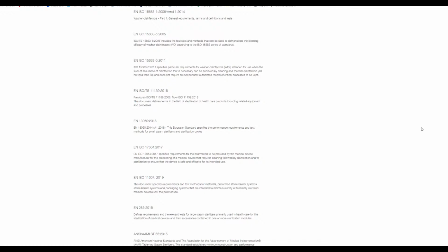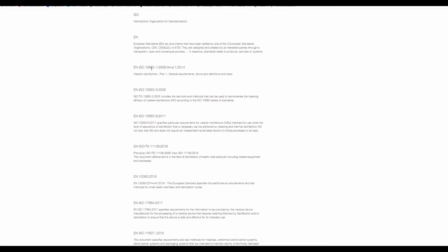What do you have to clean? Legal advice. This is, for example, the applicable standard 15883. This is the applicable standard for thermal washer disinfectors. 15883-1 is how to build a device and make it safe for use. And here, -5, this is the standard which is used to validate a cleaning process. So nice to have if you buy a machine that this machine complies with both standards.